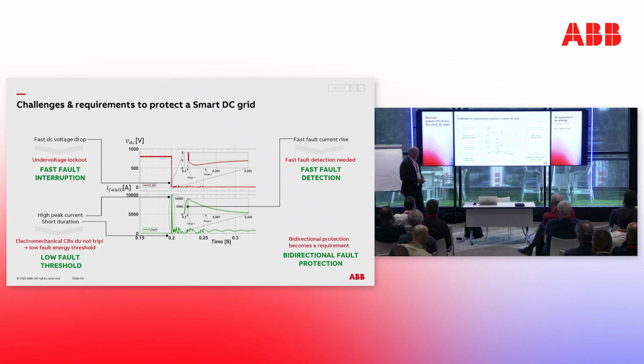Well, the problem with faults in DC is twofold. First, your current will start rising extremely fast, reaching very high peaks and releasing a lot of energy relatively fast. But at the same time, the only thing holding energy in a DC system is often the capacitor, unless you have a directly connected battery. If that's the case, your voltage is likely to collapse very fast.